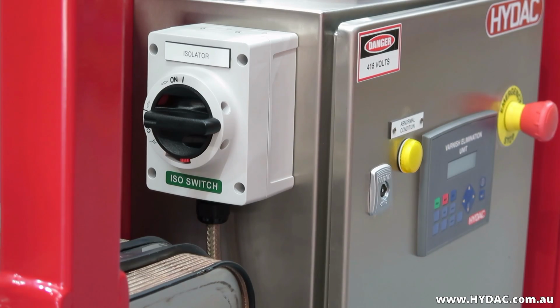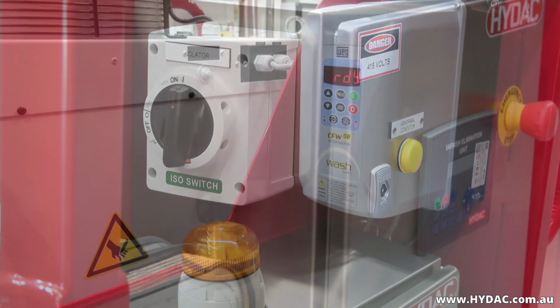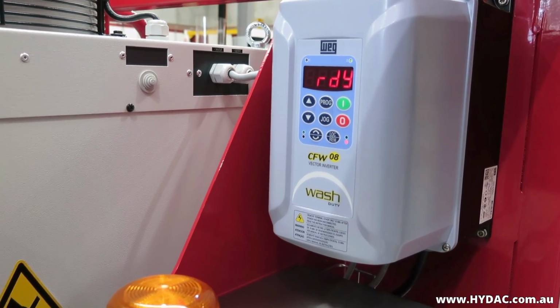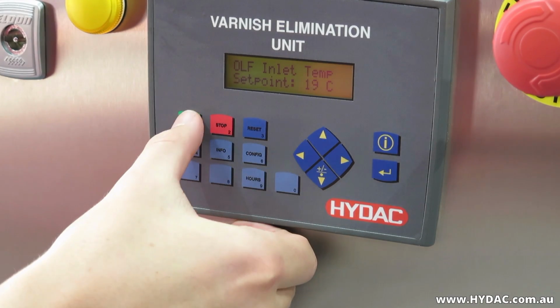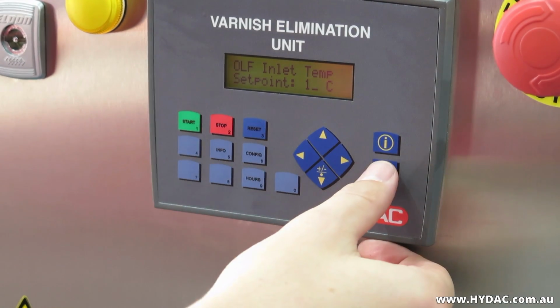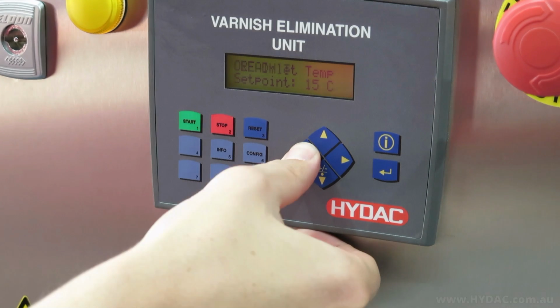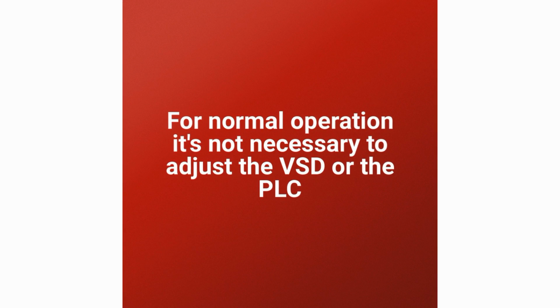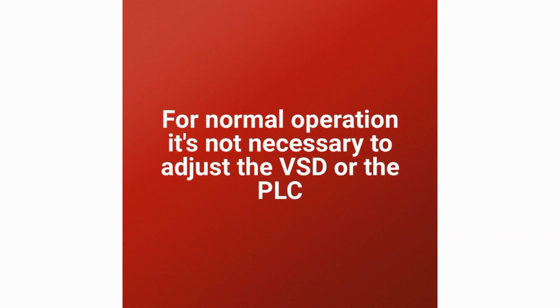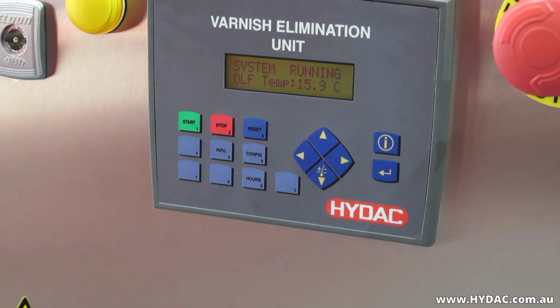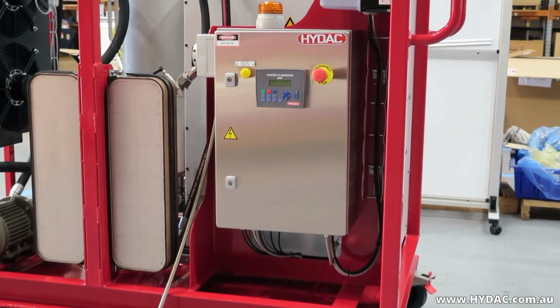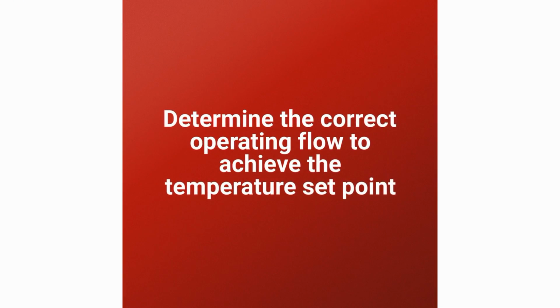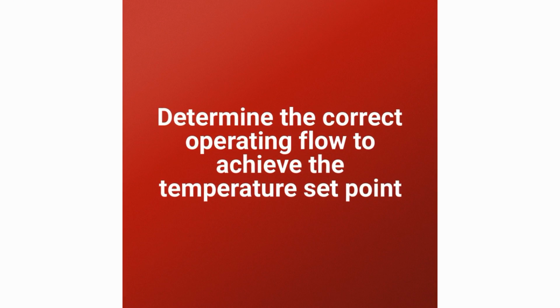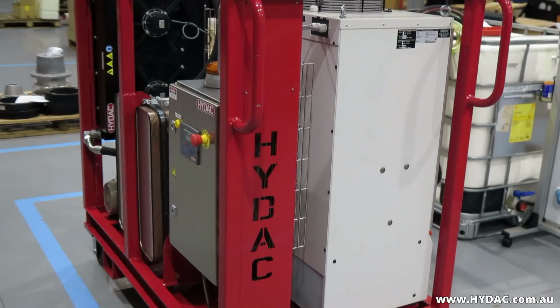Start the VEU by completing the following steps. Switch the power isolator to the on position. The PLC is set to 15 degrees Celsius as the default. If it is necessary, press the configuration button and enter the OLF inlet temperature set point from 15 to 24 degrees Celsius. For normal operation, it is not necessary to adjust the VSD or the PLC. Press the start button. The VEU will now enter a calibration phase to determine the correct operating flow rate to achieve the temperature set point. This will take 2 to 3 minutes.